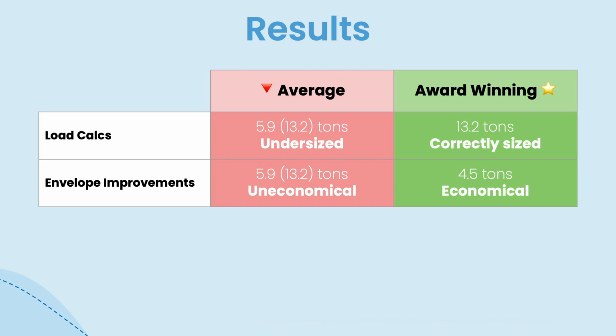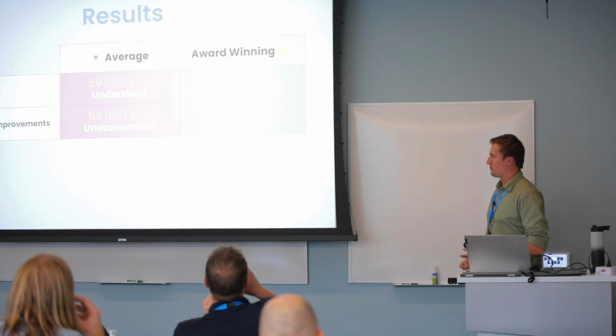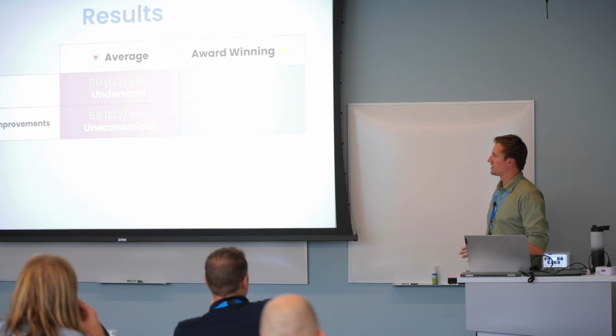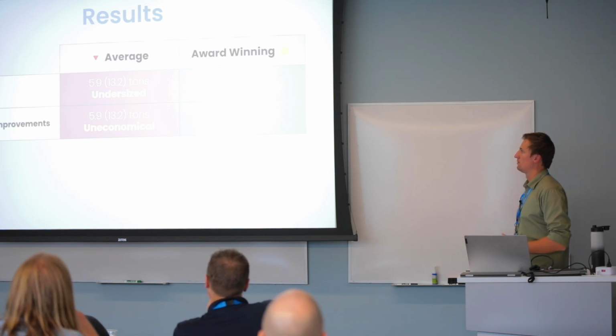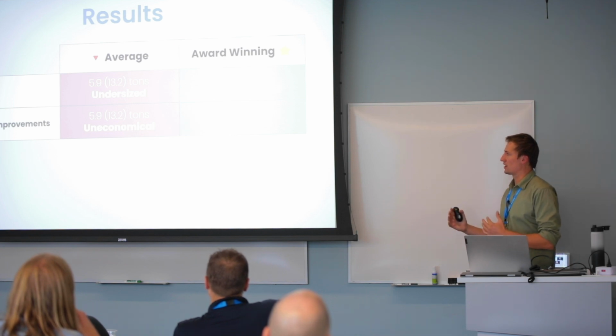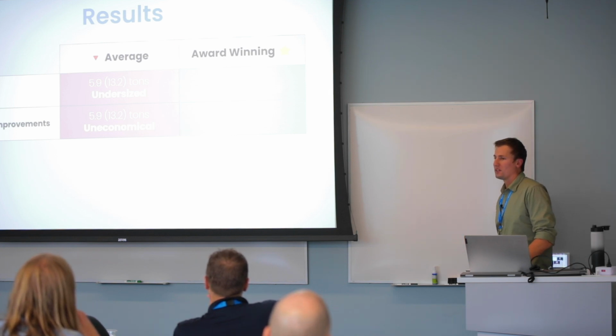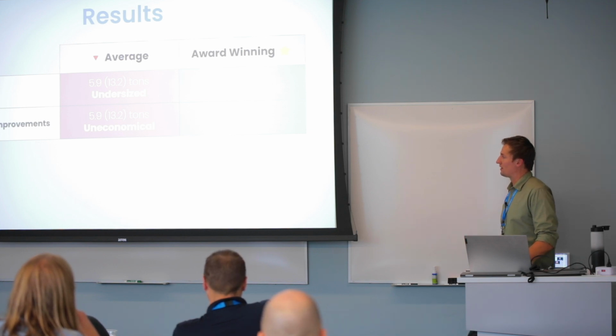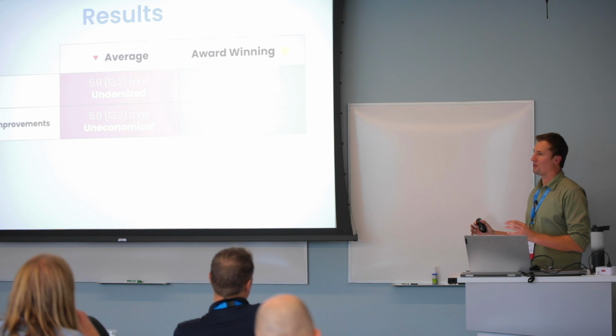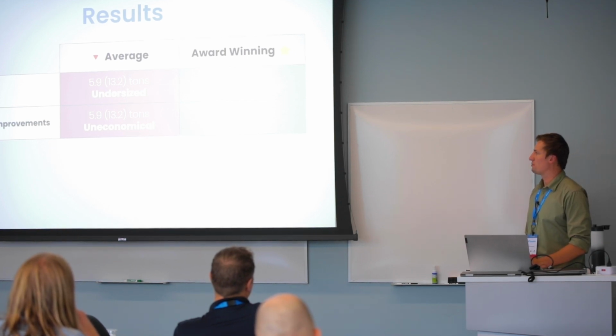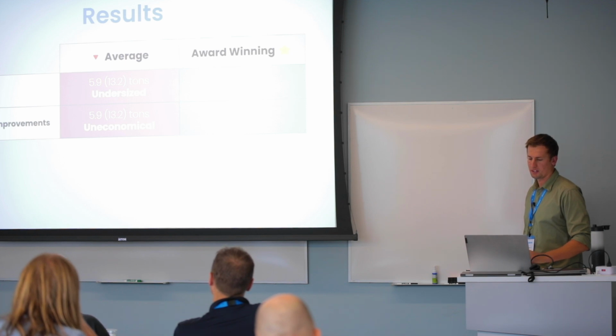So just taking a look at the results again, looking at the average one, just to remind ourselves, he didn't look at any weather data, he didn't look at the materials properly, he did a lot of rule of thumb, and that's resulted in a 5.9 ton heat pump, should have been 13.2. Arguably that's not suitable for a heat pump just because the energy usage is so high, it loses its benefits, but they've gone ahead and they're going to be recommending this anyway to the client. Whereas the award-winning one correctly sized it, and because they've correctly sized it, they've been able to design a really economical building for their client. Being able to demonstrate to them that, if you use me for this job, I know exactly how this is going to work, and I'm able to get your heat pump size down to this and lower your bills, which is probably what they want.